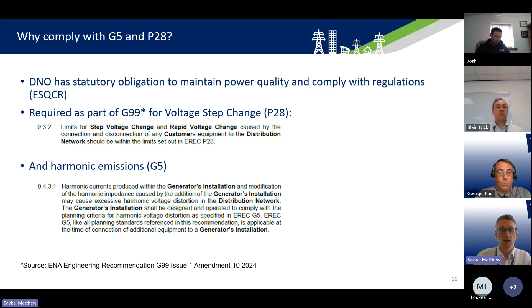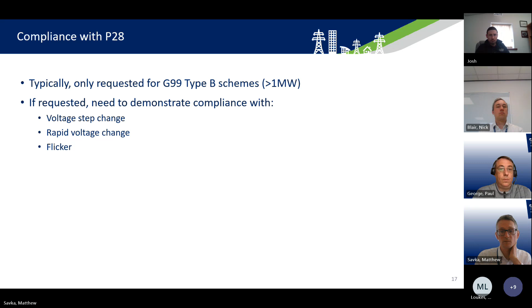To demonstrate compliance with P28, we typically only request this for larger generators, so type B G99 schemes, larger than 1 MVA or 1 megawatt. If requested, a generator would need to demonstrate compliance with voltage step change, rapid voltage change, and flicker. We do some assessment of that at the quotation stage, just to ensure that no generator connected is going to impact voltage step change.